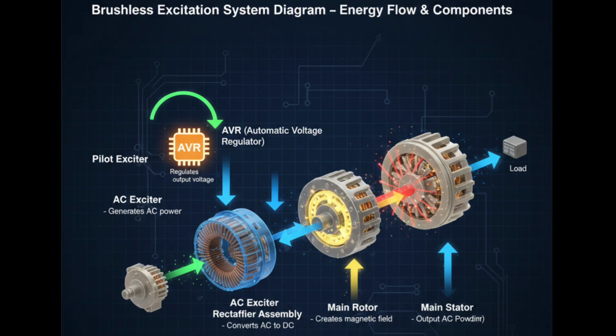Blue arrows indicate AC current from the exciter. Yellow arrows indicate rectified DC to the rotor. Red flux lines show magnetic field generation. Notice the feedback loop from the stator to the AVR. The AVR senses output voltage and sends signals to adjust the rotor field automatically.